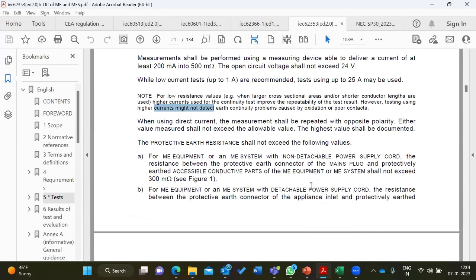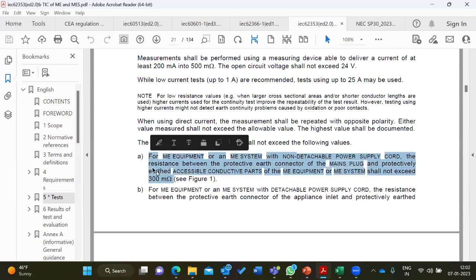For example, here, for medical electrical equipment, I'm reading the clause: for medical electrical equipment or an ME system with a non-detachable power supply cord, the resistance between the protective earth connector in the mains plug and protective earth accessible conductive parts of the ME equipment or ME system shall not exceed 300 milliohm. So this is a requirement for one type of equipment.